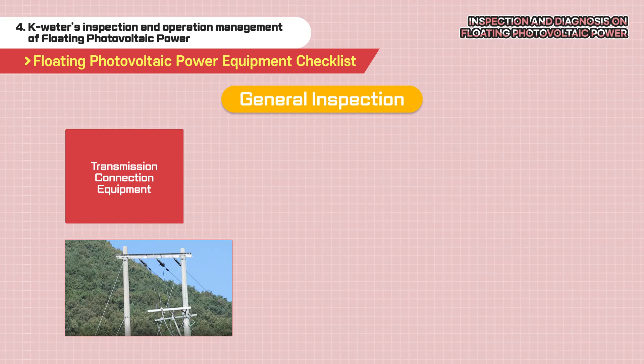The power transmission connection equipment is used to convert direct current produced by floating photovoltaic power modules into alternating current through inverters and transform it into a voltage suitable for the KEPCO system and transmit it. It consists of outdoor panels, inverters, transformers, breakers, and protective relays.